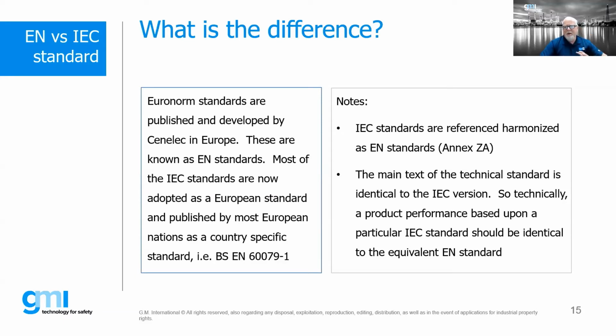So what this boils down to is: does that mean if I have a product built to an IEC standard, I can automatically just take that and use it in Europe? Not necessarily. But what it does mean from a technical standpoint is, if I've built a flameproof box to the Dash 0 and Dash 1 standards, I'm not going to have to go above and beyond technically to comply with the Euronorm standards. I may have to do some additional quality work, some additional markings, and there'll be a different cert issued for it, but the actual technical details of what constitutes a flameproof box will be identical.